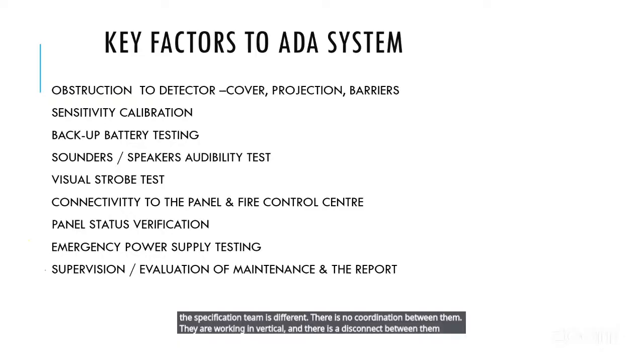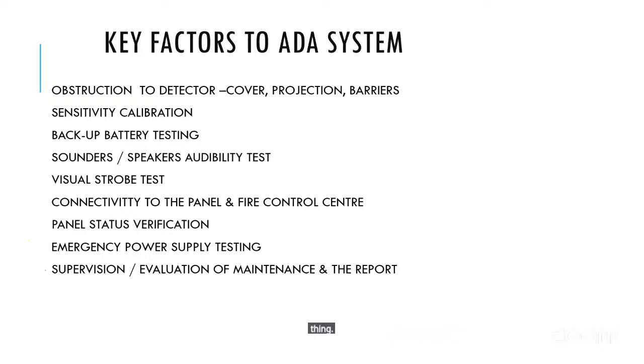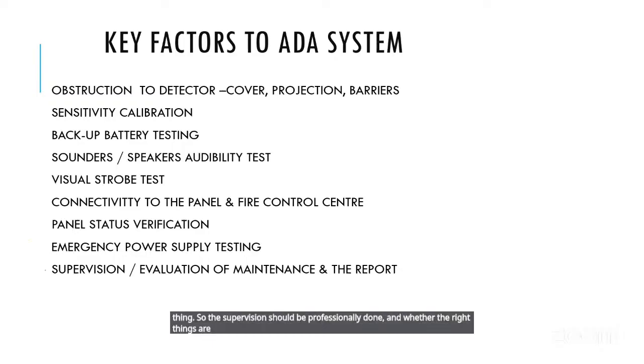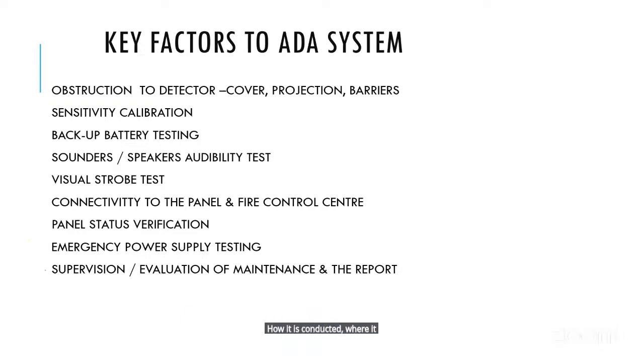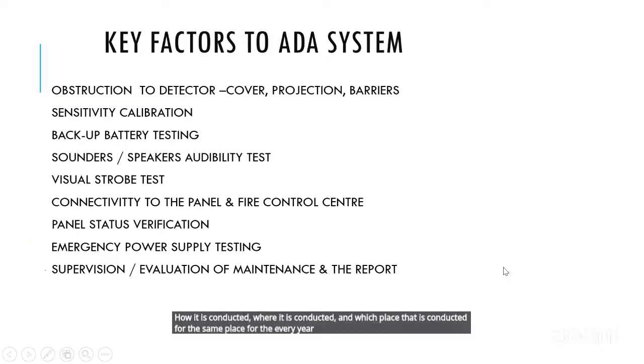That is the thing. So the supervision should be professionally done, and it must be supervised whether the right products are coming and whether they are installed the right way. That is the first thing. Second thing, evaluation of maintenance. When an extinguisher is maintained, a sprinkler is maintained, when the flow test is conducted for the sprinkler, how is it conducted, where is it conducted, which place is it conducted? If it is the same place every year, what is the fun in conducting those tests? So those things must be understood properly.